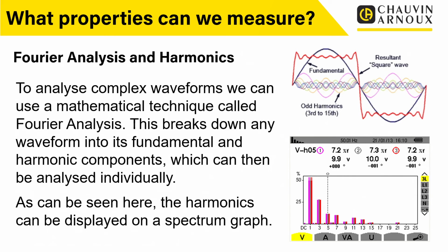So this is quite a clever technique, and the technique means that basically we can break down any waveform, any shape waveform. So you can see on the top right there, we've got a waveform that looks almost like a square wave, but that's actually made of multiples of other frequency waveforms added together. Now, what we can do is we can sort of do it the other way around. If we want to know, well, what's causing this waveform not to be a sine wave? What's causing this waveform to look distorted?